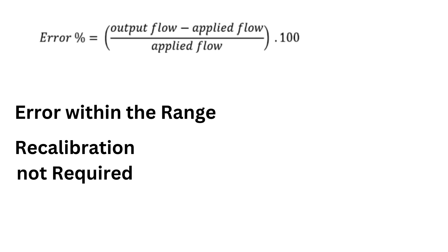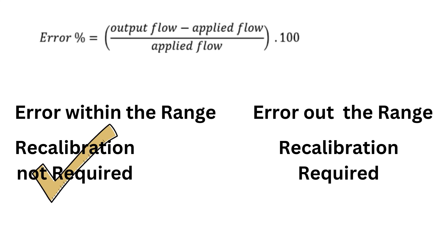Now calculate the error percent from the flow values we got with the next formula. If the calculated errors are all well within the required accuracy for the application, then the DP type flow transmitter is okay and should not be recalibrated. If the error obtained from the calculations is more than the required accuracy for the application, then a calibration of the DP flow transmitter is needed.